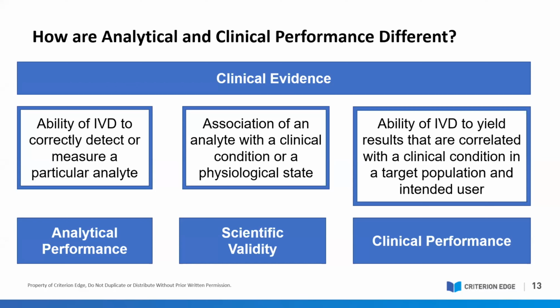And for some devices, the CPR may not be required, particularly for Class A devices. So that can add an extra point of confusion for some. The term clinical evidence by itself can be confusing because a clinical study is sometimes just a broad blanket term applied to any study collecting or using patient samples, independent of those performance indicators. But an analytical performance study utilizing patient samples is still an analytical performance study. It's not considered to be a source of clinical performance data.